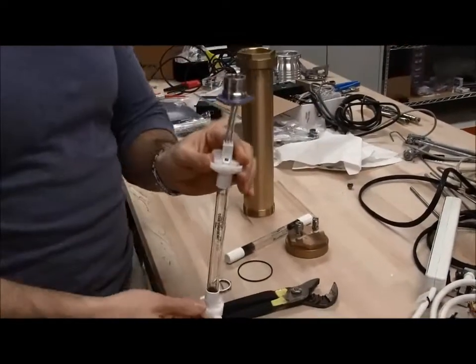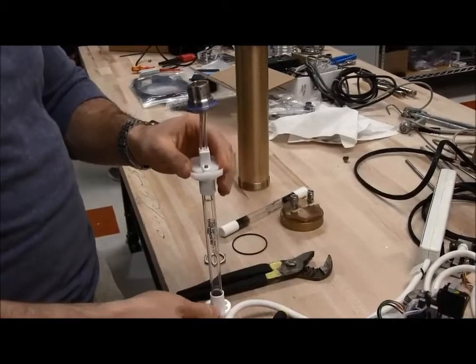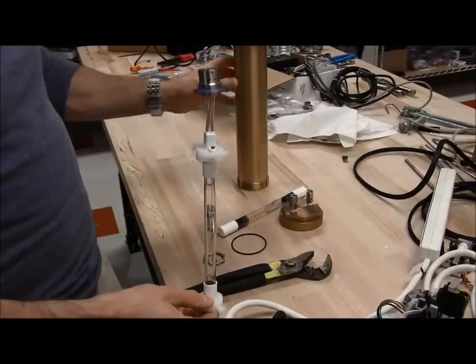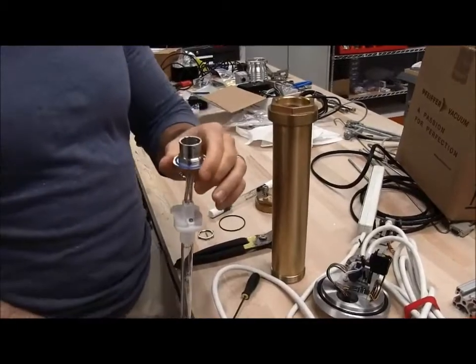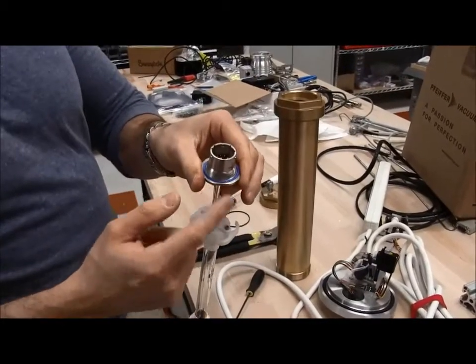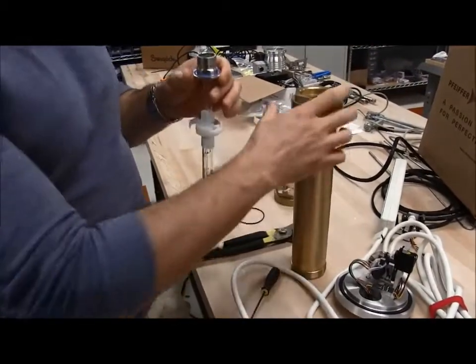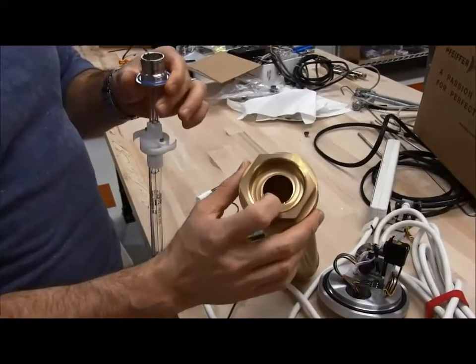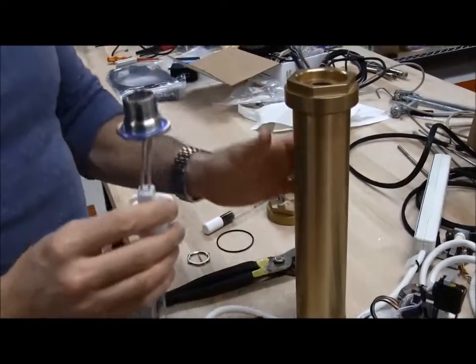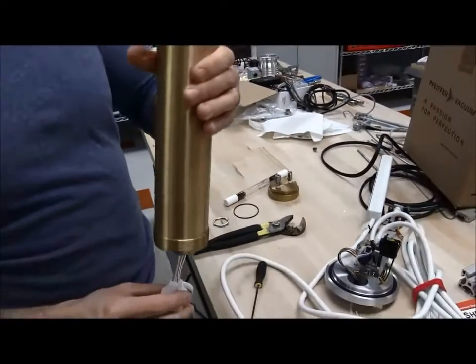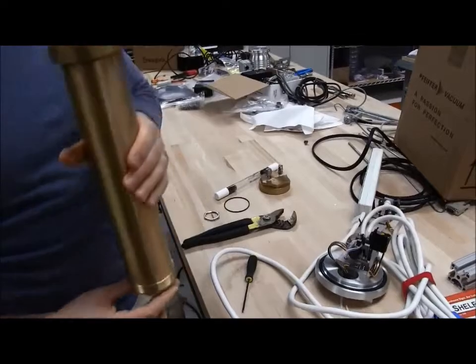So now you're ready to reassemble the lamp inside the ozone chamber and this will take a little bit of practice but basically the most important part is this flat cutout on the connector you want to try to line up as best as possible with the corresponding part on the cutout here before you push it in so that you minimize the amount of twisting that you have to do.